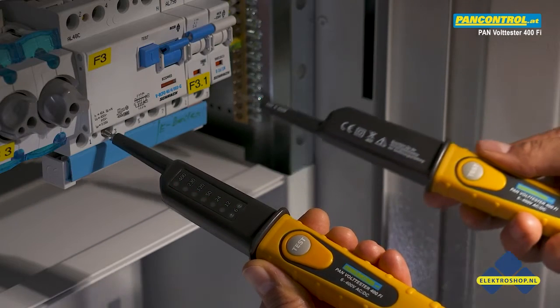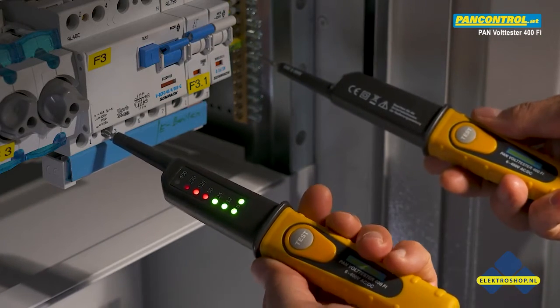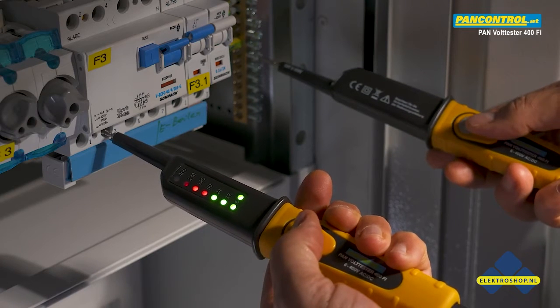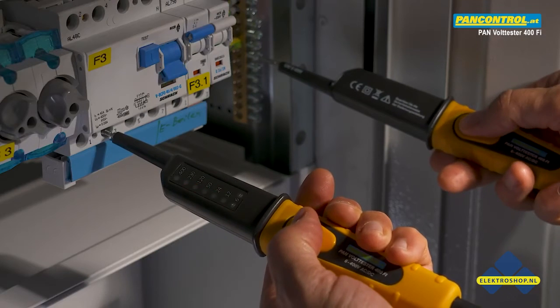While testing voltage between one phase and the earth, you can increase the testing current to 30mA by pressing the two test buttons. This will cause a 30mA RCD switch to trip.